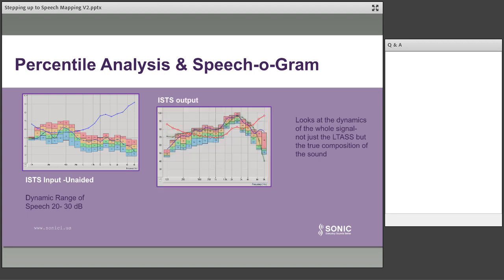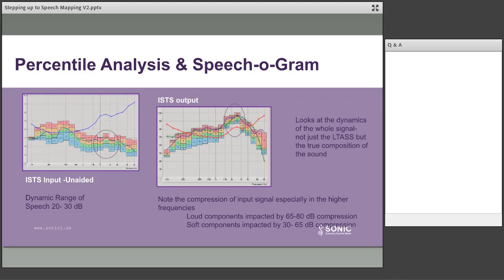Now, if we were to then put the hearing aid in and measure what's happening to that input signal once it's gone through the hearing aid, then we can see a different picture. Especially in the high frequencies, you can see that the input signal's dynamic range is much bigger. And when we look at the aided level, we can see that those high frequency signals are much more compressed, because the area of that curve is much, much smaller. So we know that when we put a 65 dB speech signal in, the loudest parts of that signal are going to be affected by the 80 curve and the compression above, and the softer parts of the signal are going to be more affected by the 50 curve from below.